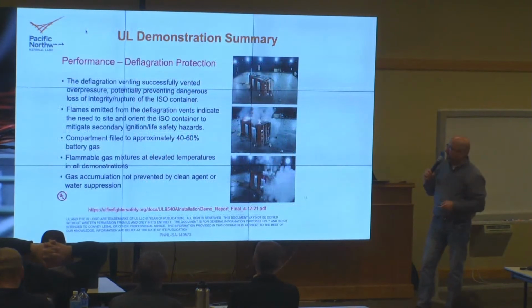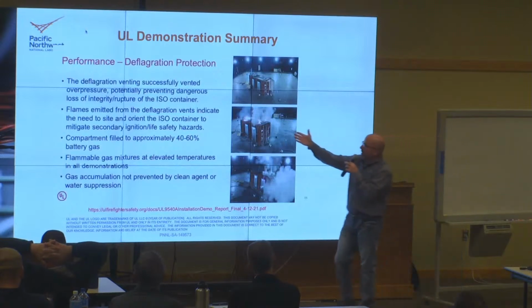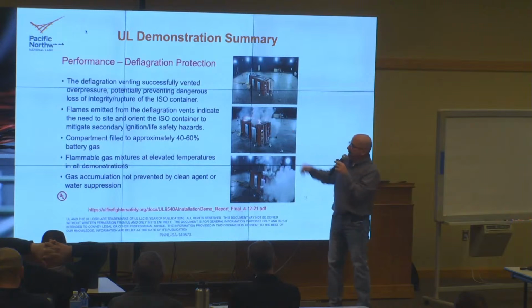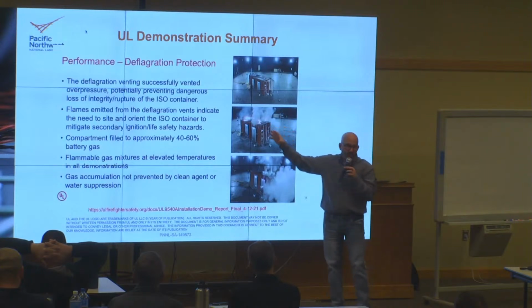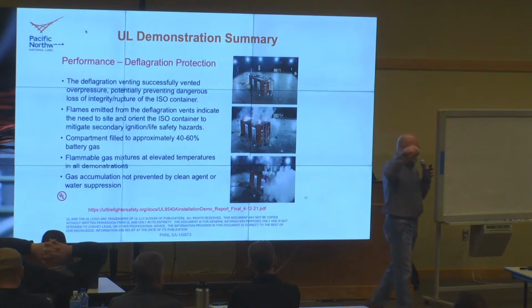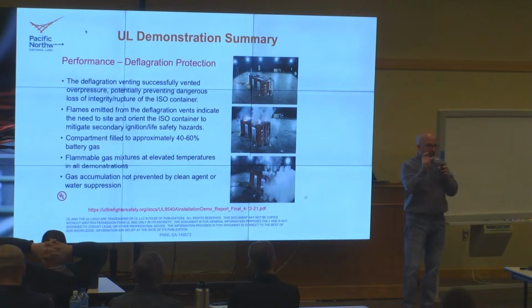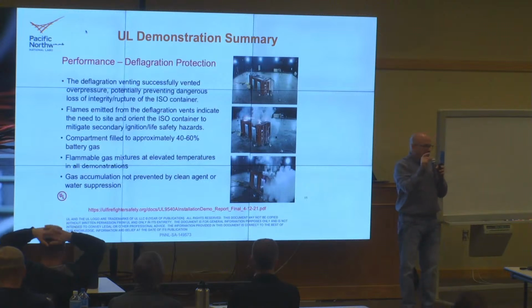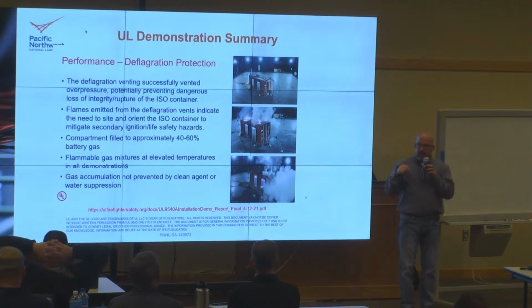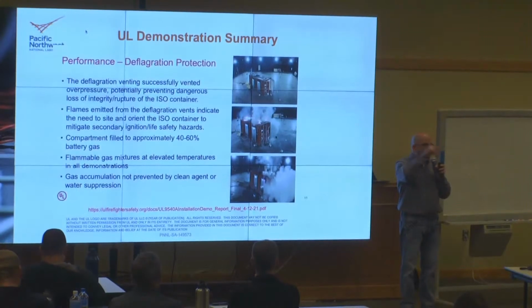So the bottom line is that the deflagration vents operated, here's even flames coming out of them, in each of the tests, all right? They had the compartments filled between 40 to 60% of gases at elevated temperatures. And let me say one thing. The thermal runaway temperature of a cell very often reaches the autoignition temperature of hydrogen. So you could have a thermal runaway with no flames, but just the temperature of those gases coming out could ignite the hydrogen that's coming out.